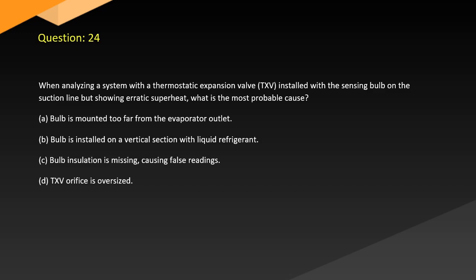Question 24. When analyzing a system with a thermostatic expansion valve, TXV, installed with the sensing bulb on the suction line but showing erratic superheat, what is the most probable cause? A. Bulb is mounted too far from the evaporator outlet. B. Bulb is installed on a vertical section with liquid refrigerant. C. Bulb insulation is missing, causing false readings. D. TXV orifice is oversized.